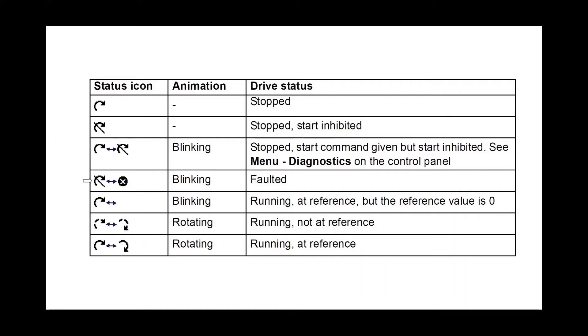The curved arrow with a line through it blinking between an X means that the drive is in fault. A curved arrow that is blinking means it is running at reference but the reference is at zero. A dotted curved arrow blinking between a dotted rotating arrow means the drive is running but hasn't reached the reference yet. Once it reaches the reference, the arrow will turn solid again and keep rotating.